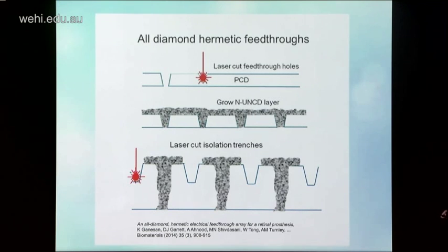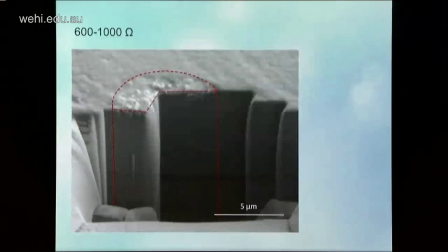You can grow this for a certain amount of time, say overnight, and if you take it out in the morning and test it and it's still leaking, you can still pass helium through it. You simply put it back into the reactor, give it another day, and eventually all the holes will close up and you'll have yourself a hermetic array. So a nice, reliable, and extremely testable system.